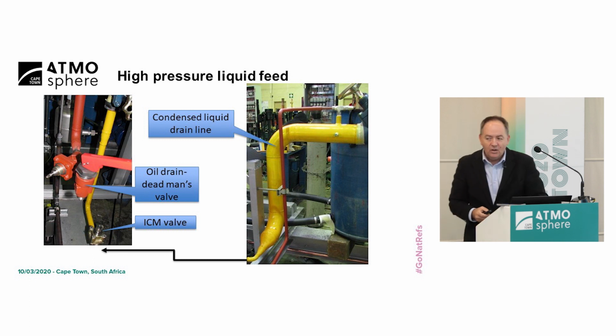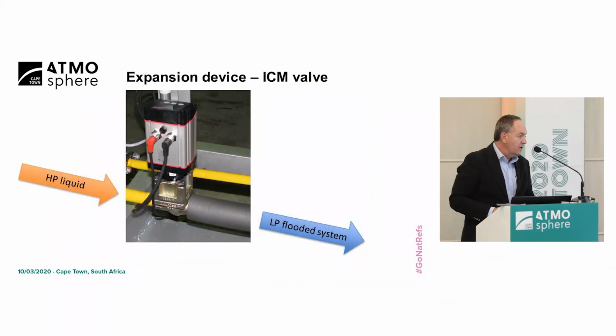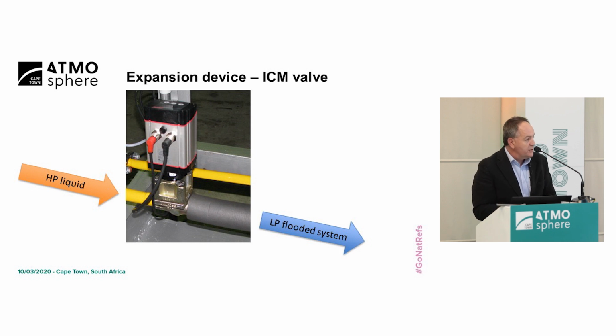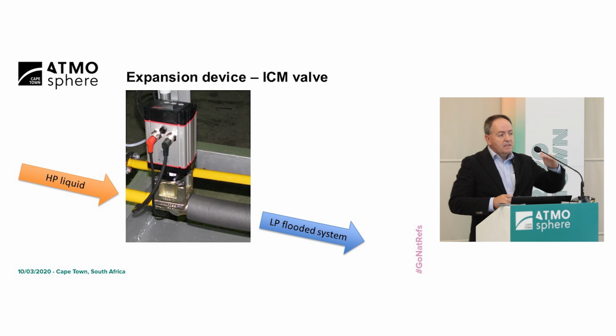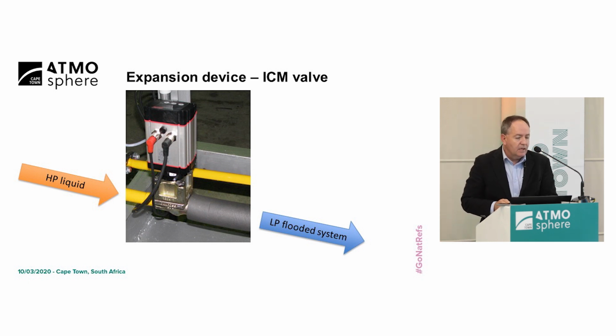Our ICM valve is our expansion device in this case. You see that yellow pipe, that's our high pressure liquid feeding to the expansion device, and that expansion device then feeds the heat exchanger. So we electronically control the liquid level, and in this case we have a range of 280 mil. We had no liquid receiver. That drain line you see there is the drain line coming from the evaporative condenser. So we have no liquid receiver in this case.